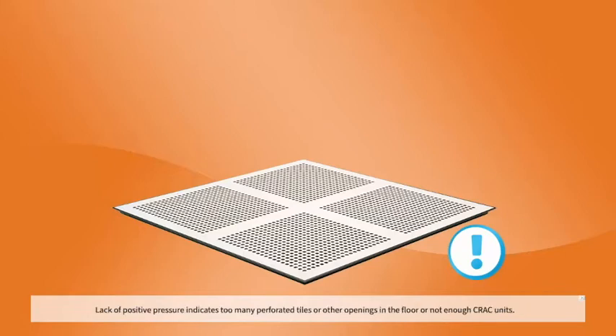Lack of positive pressure indicates too many perforated tiles or other openings in the floor, or not enough CRAC units.